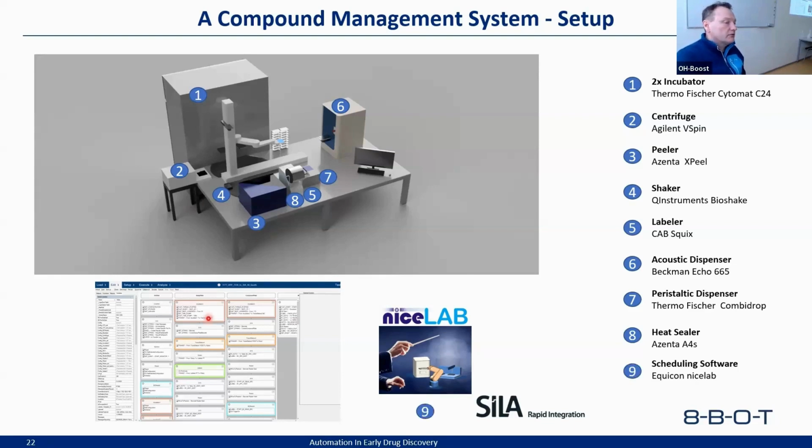And at the end, we have scheduling software, orchestration software, which controls the different parts of it. This one is from a company in Jena in Germany, and this system is completely based on SiLA. So this is a system where you can take a device that speaks SiLA and integrate it here. For sure, you have to pay for the connector, so you cannot just use 10,000 devices. This is the point where they're making money. They say, okay, we sell you a basic system, but for every separate device you want to add, you have to pay something. But the rest is open, so you can write your own driver and integrate it here. So you're not dependent on the vendor.